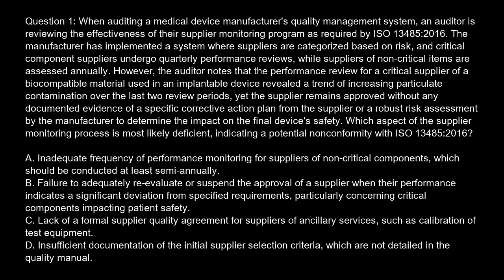However, the auditor notes that the performance review for a critical supplier of a biocompatible material used in an implantable device revealed a trend of increasing particulate contamination over the last 2 review periods, yet the supplier remains approved without any documented evidence of a specific corrective action plan from the supplier or a robust risk assessment by the manufacturer to determine the impact on the final device's safety.